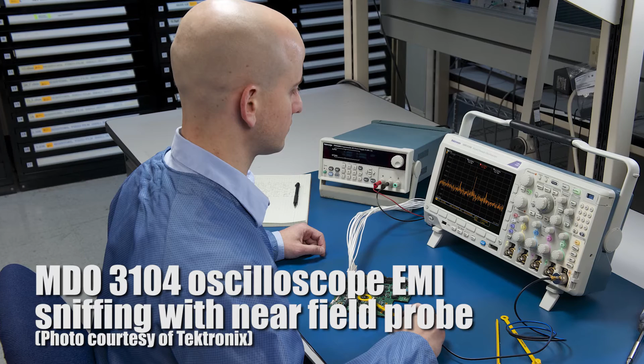To begin, connect one end of a BNC cable to the AFG output on the back panel. Connect the other end to the channel 1 port on the front panel. Push AFG, the bottom button in the column above the channel 1 analog input port. If the oscilloscope has been defaulted since its last use, you have to start from scratch on the AFG. Press waveform and make sure that it is highlighted.